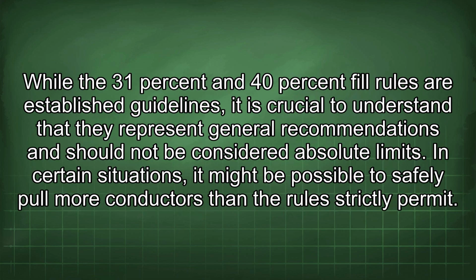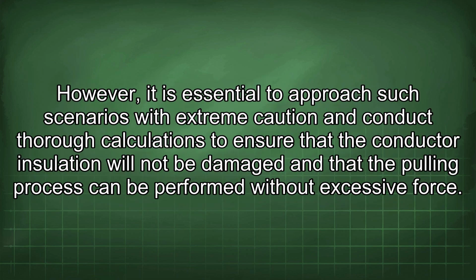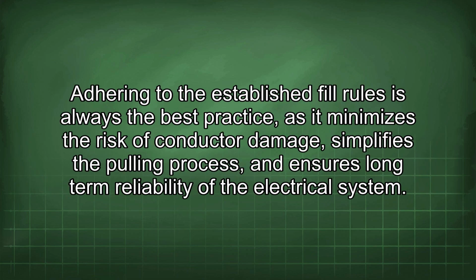While the 31% and 40% fill rules are established guidelines, it is crucial to understand that they represent general recommendations and should not be considered absolute limits. In certain situations, it might be possible to safely pull more conductors than the rules strictly permit. However, it is essential to approach such scenarios with extreme caution and conduct thorough calculations to ensure that the conductor insulation will not be damaged and that the pulling process can be performed without excessive force. Adhering to the established fill rules is always the best practice, as it minimizes the risk of conductor damage, simplifies the pulling process, and ensures long-term reliability of the electrical system.